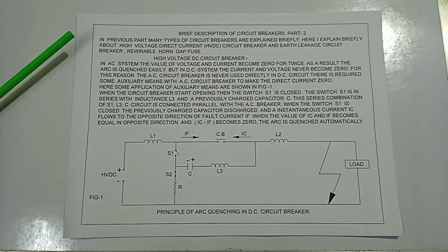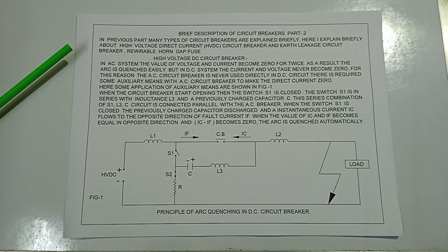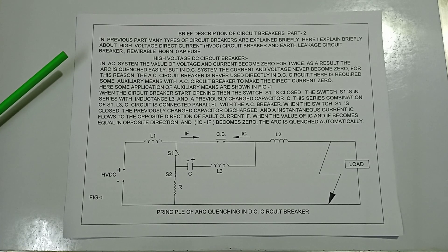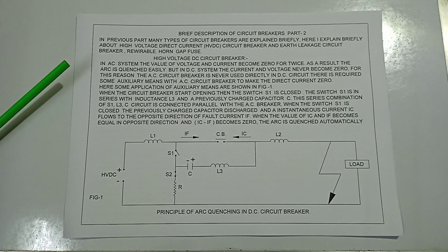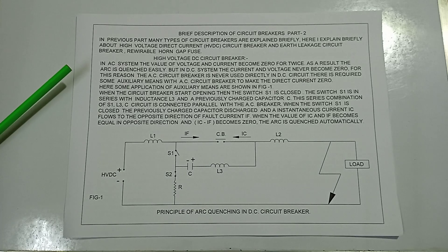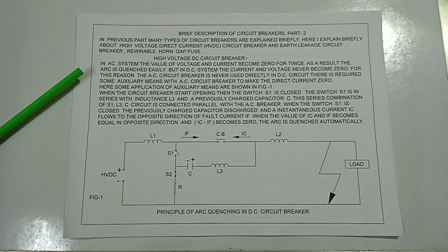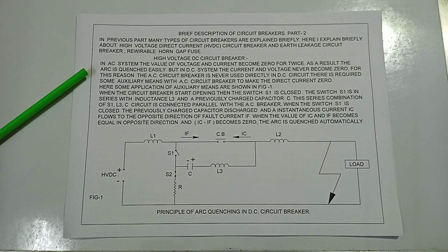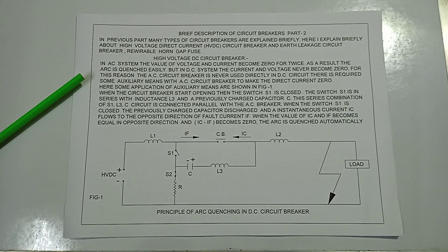In the previous part, many types of circuit breakers were explained. Here I explain briefly about high voltage direct current (HVDC) circuit breakers. In an AC system, the value of voltage and current become zero twice per cycle, so the arc is extinguished easily. But in a DC system, the current and voltage never become zero, so an AC circuit breaker can never be used directly in a DC circuit.